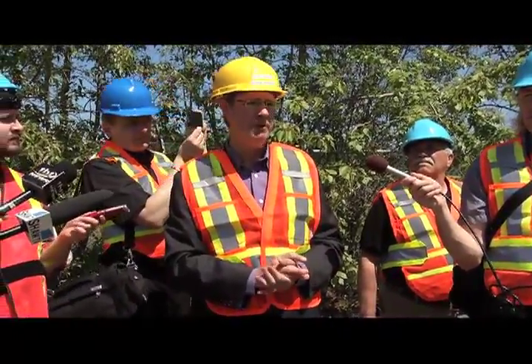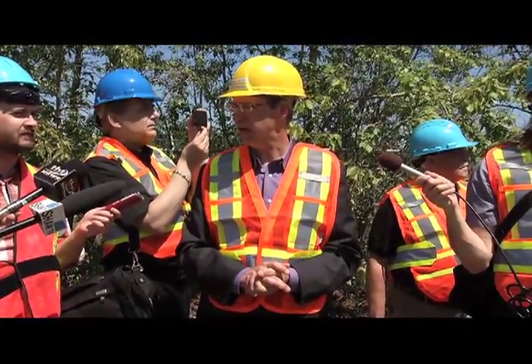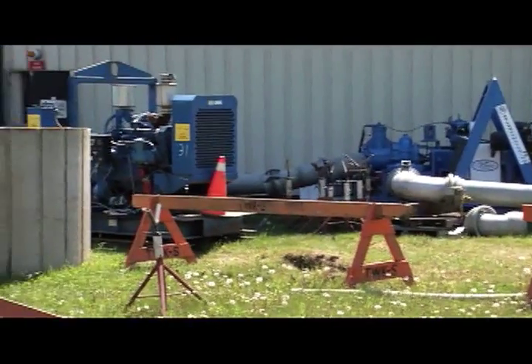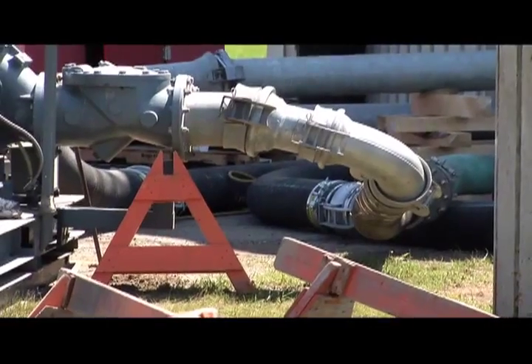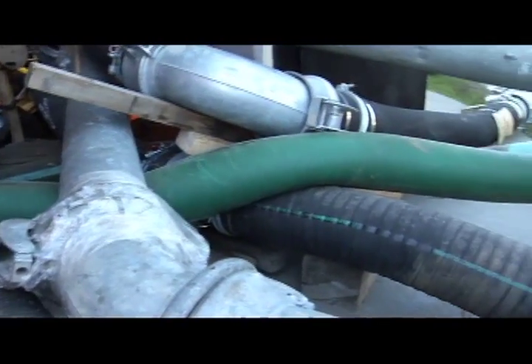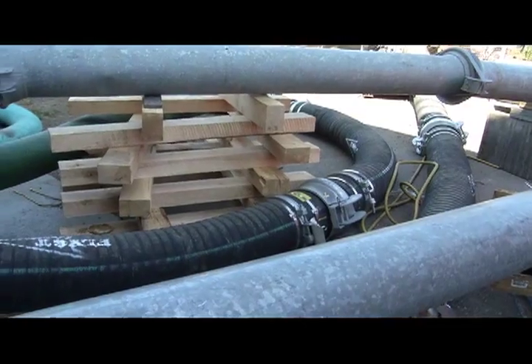What you see set up here right now is all the temporary pumping that we put in on May 28th and 29th. You can see pump 31 and these big red ones — they've got a suction pipe going into the wet well. As we walk around, you'll see their discharge pipes go around the corner; some go into the building, and they're pumping all of the stormwater that came in here that morning to an overhead channel and through the treatment process.